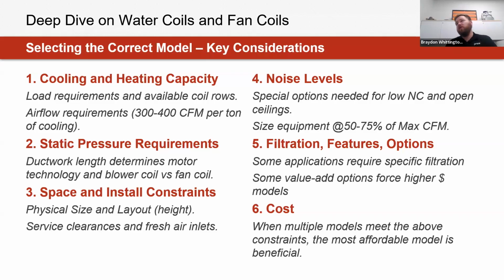Space limitations are next, in terms of height or overall size of this equipment, if we're all of a sudden trying to bump up to the next unit size to achieve that same capacity. Noise levels, we already mentioned, of selecting a certain point within the curve to make sure that we don't have any unwanted noise coming from it. Filtration, different options there too, and hanging accessories. And then finally, also a key consideration, cost. That does the cost analysis.